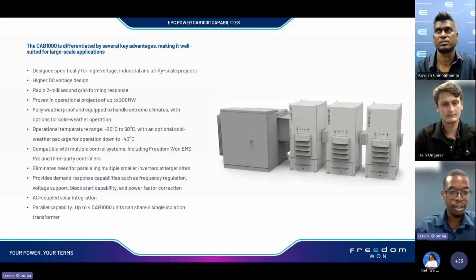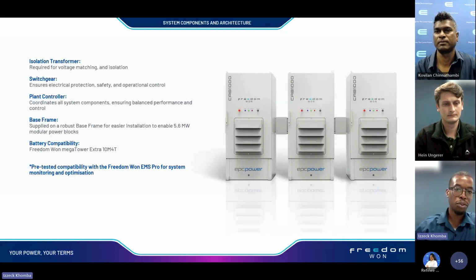Thanks, Hein, for taking us through the key advantages of the CAB1000. As we can see, it's quite a scalable inverter and suitable for microgrid application. So we're going to look at some of the system components which are required when rolling out the CAB1000 into various projects. One of them that's very important is the isolation transformer. So this needs to be spec'd correctly to match the application to be integrated with the CAB1000.